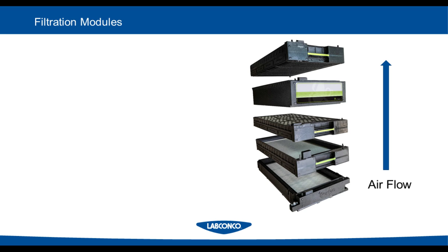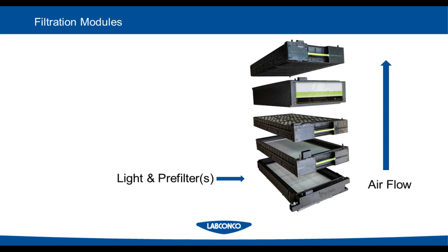This is a module or stack of filtration technology sitting on top of the filtered fume hood. And starting at the bottom, you first off have a light. The hood users need to see what they're doing, of course. And then above that light will be some pre-filters. There are optional different pre-filters. We'll talk about that in a couple slides. And then on top of that base module would be a HEPA filter if you're working with hazardous powders. This is not required, this is optional.